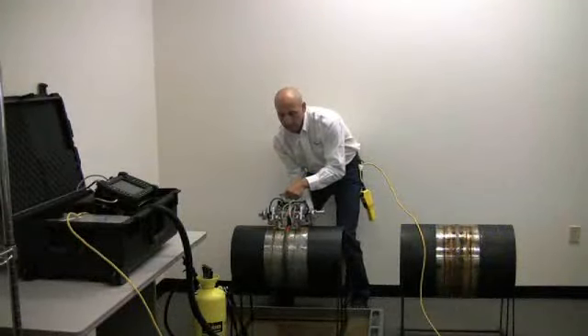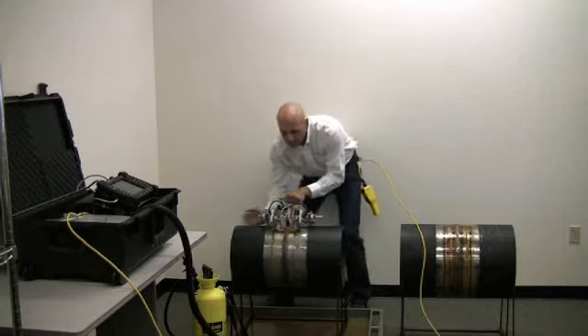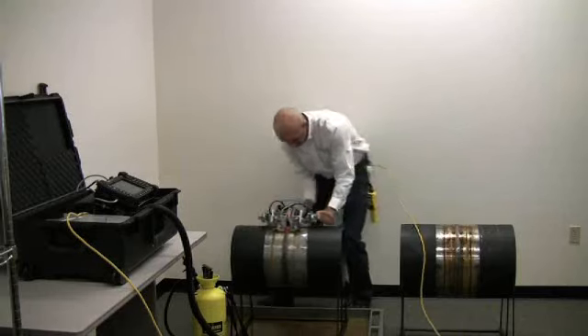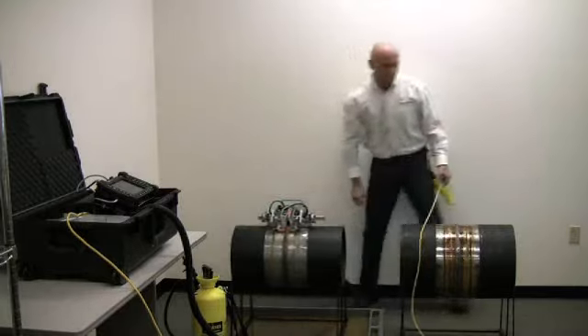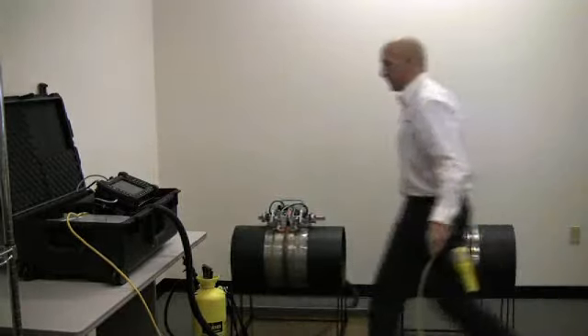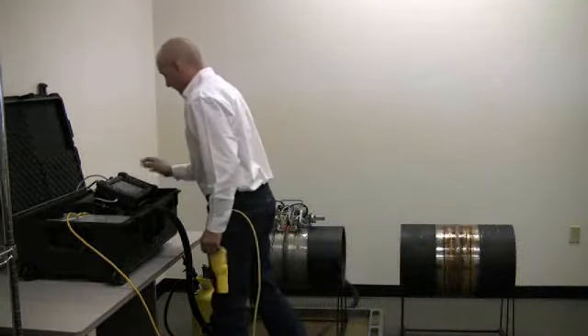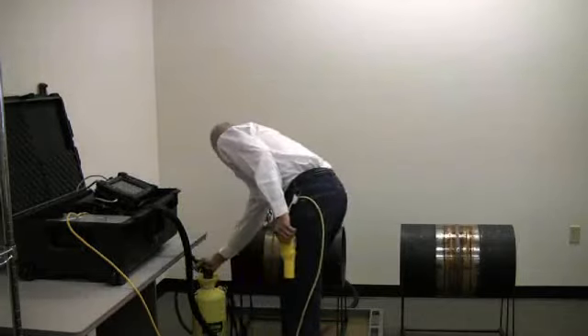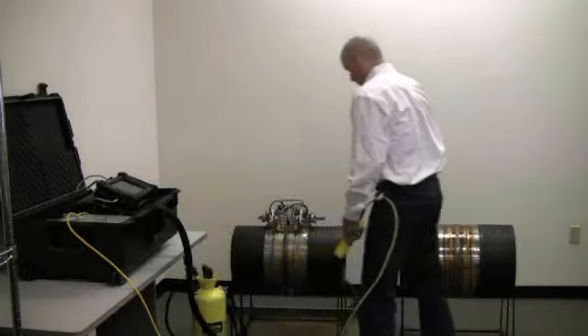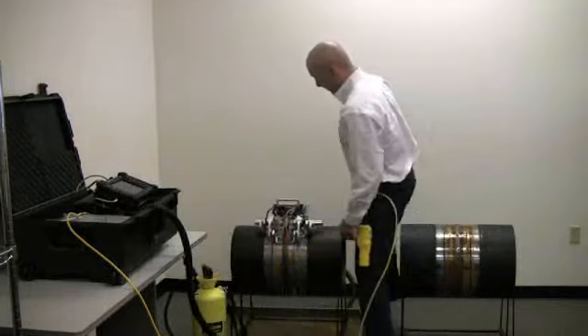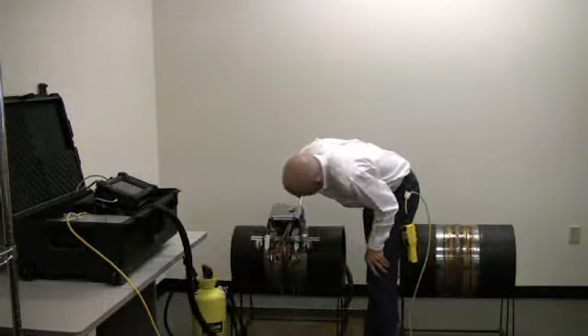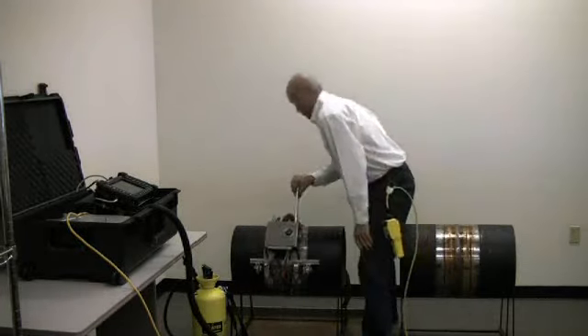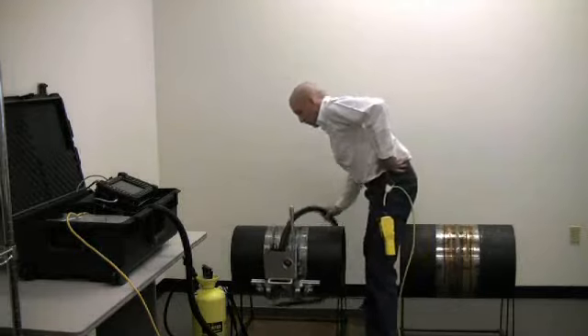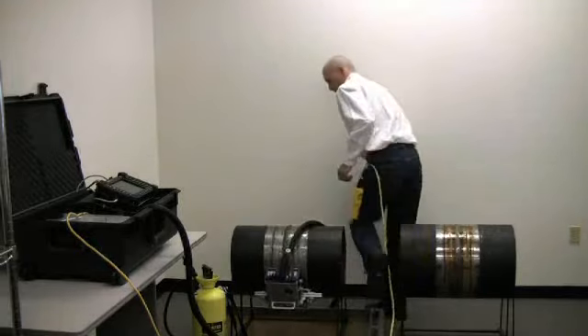Align the laser on the center line of the weld, gently place the footprint of the probes in place. Verify that the laser is aligned with the weld. Preparing the OmniScan for start acquisition, enable the water supply, ensure your cabling and remote aren't obstructing the scanner, visually verify the laser is tracking on the weld, apply a pressure on the guide bar if necessary.